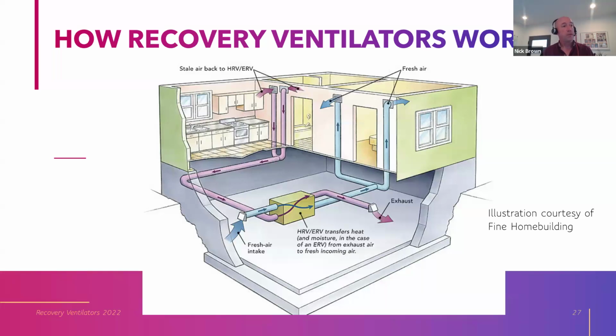At the same time, a different fan in the box is pulling stale air out of the house. Generally, the kitchen and the bathrooms are those spots that are chosen because they're spots with additional moisture that needs to be removed, right? Also smells, but mostly for the moisture. And then that pink ductwork goes into our box. The two streams swap heat to some extent, not 100%. This is the term called recovery effectiveness that measures what portion of the delta in temperature between the two air streams is captured. Okay, and if it's an ERV, they're also swapping some of that moisture, right? And then that stale air continues out of the building.